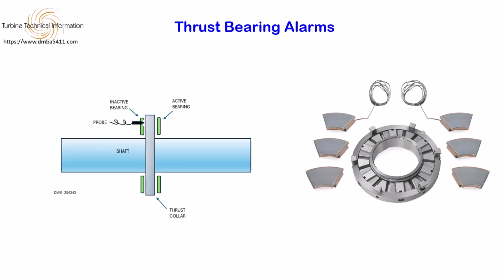The rotor is moved to the limits of its travel within the bearing, and the voltage is noted at either extremity. Then if the alarm is 0.003 of an inch of wear into the bearing, 200 mV multiplied by 3 gives 600 mV, which is added to or subtracted from the voltage obtained when the rotor was at the extreme of its travel. This DC voltage now represents the voltage that the channel must reach before the alarm.